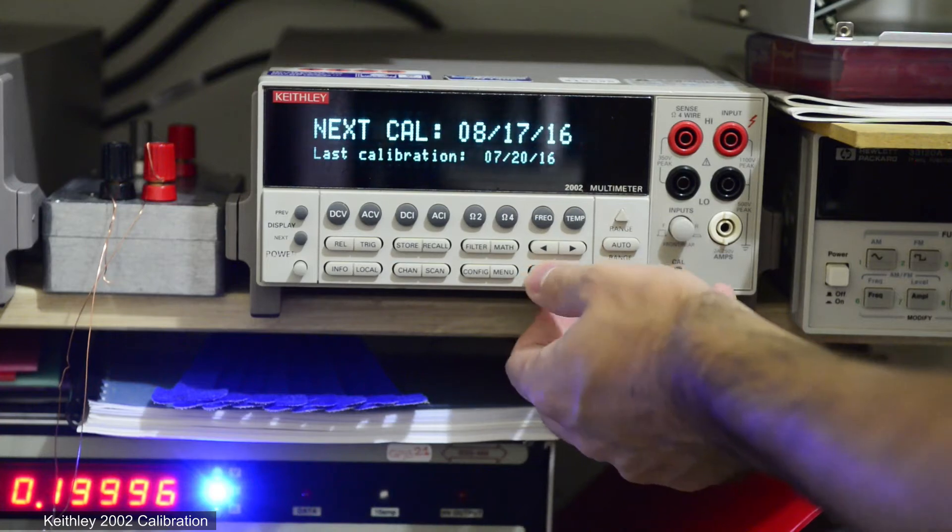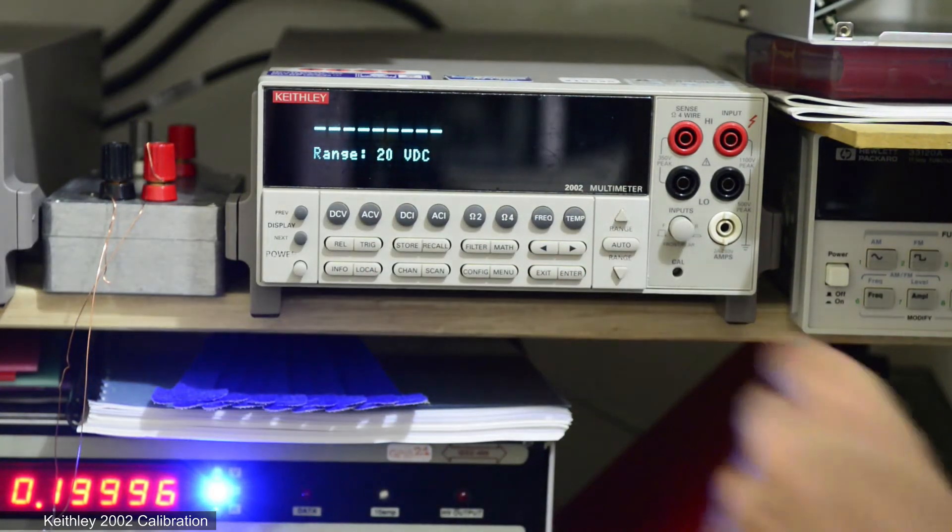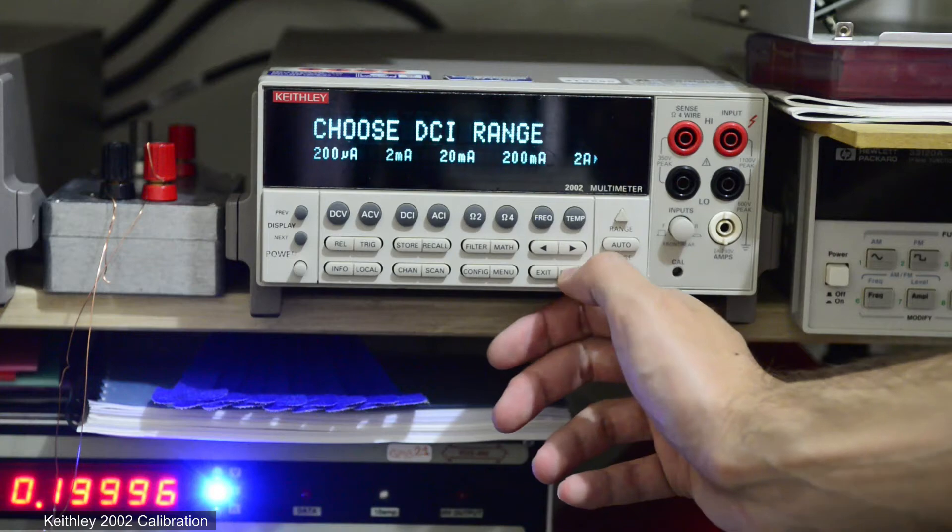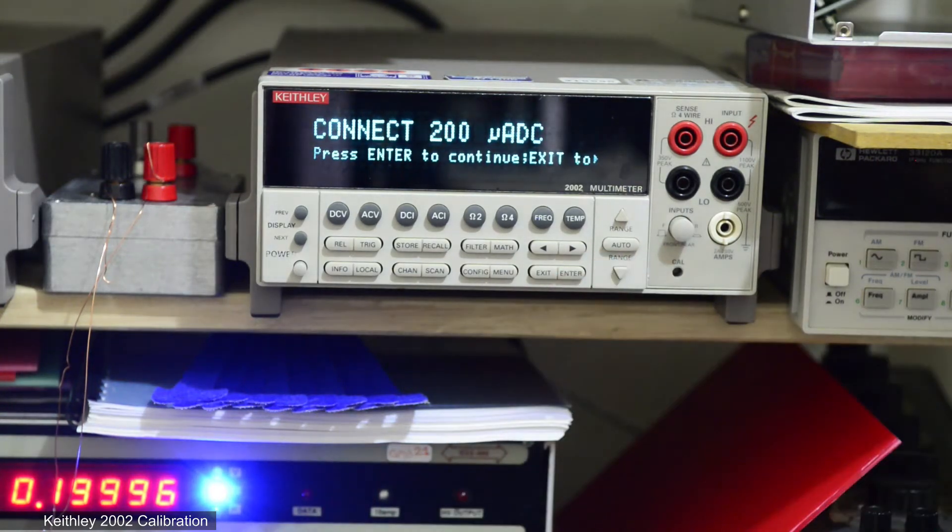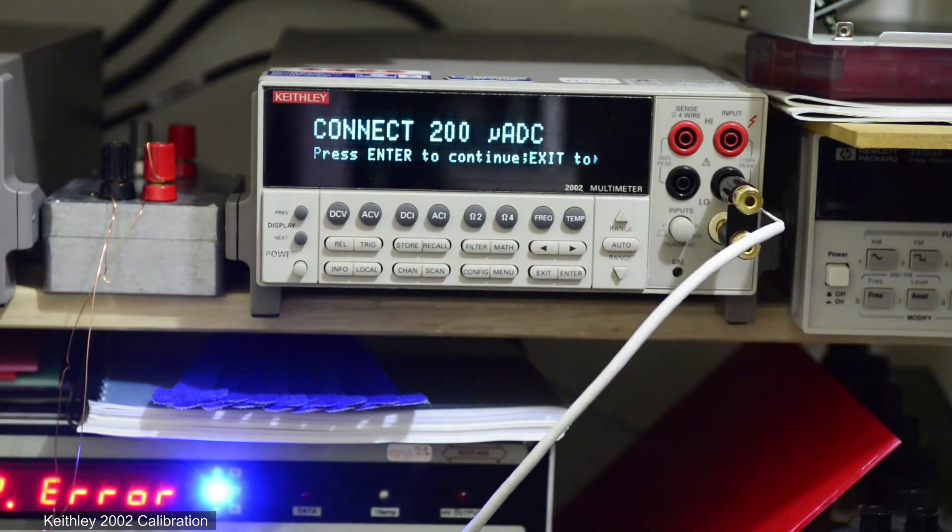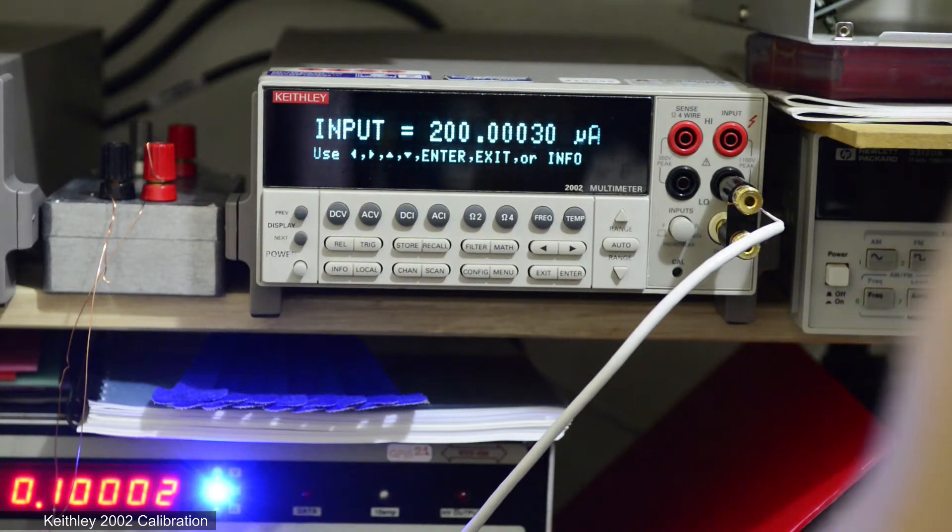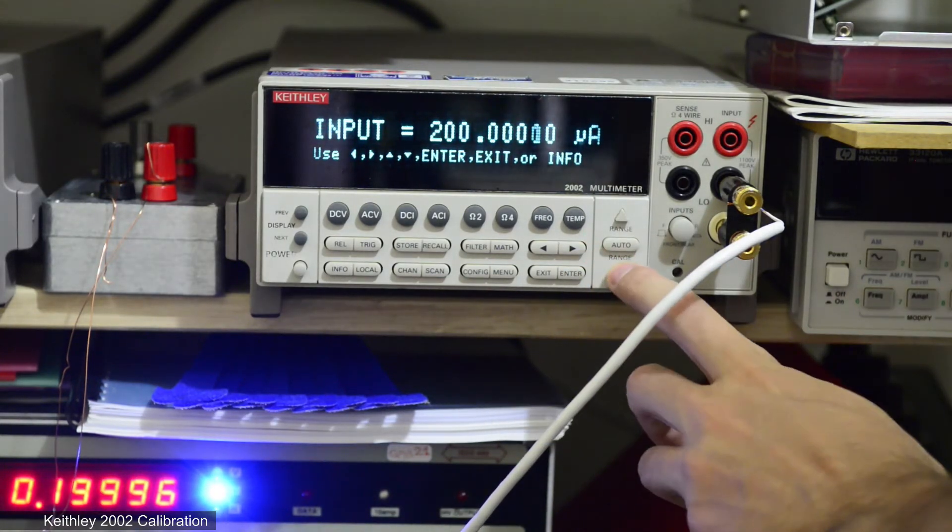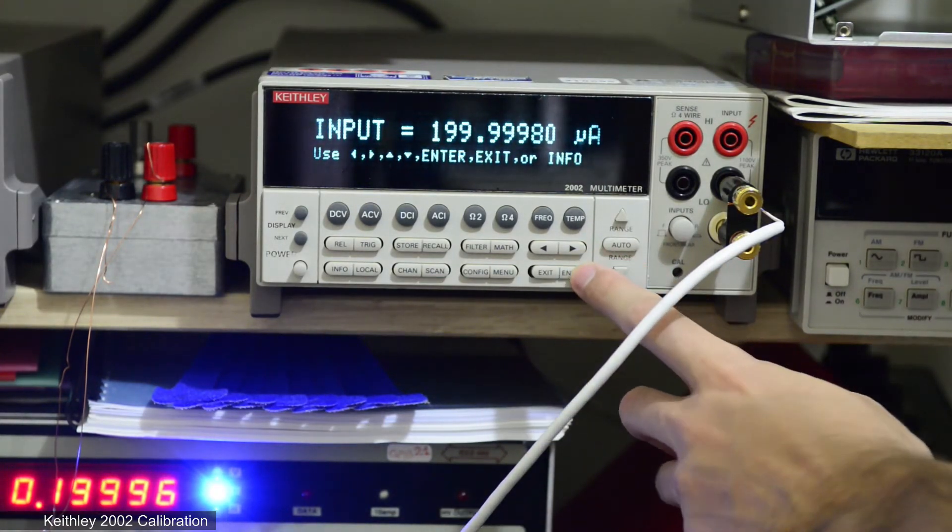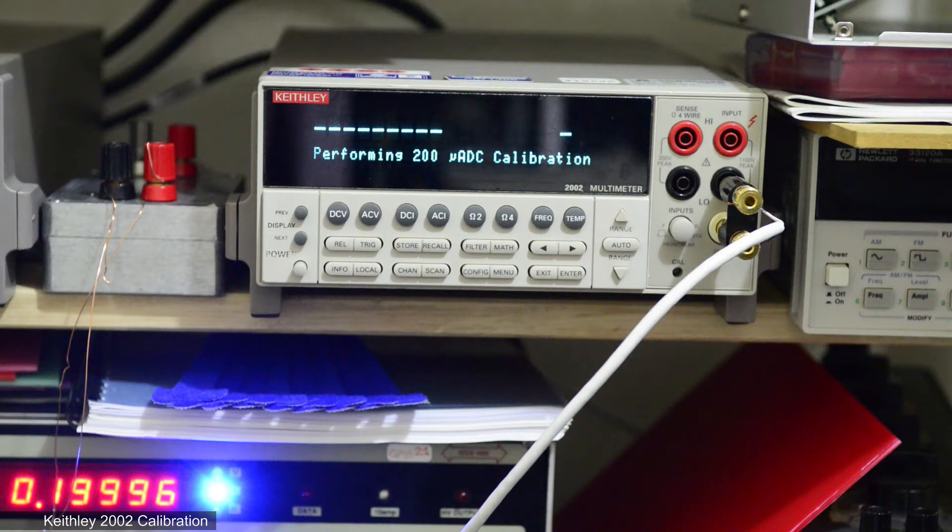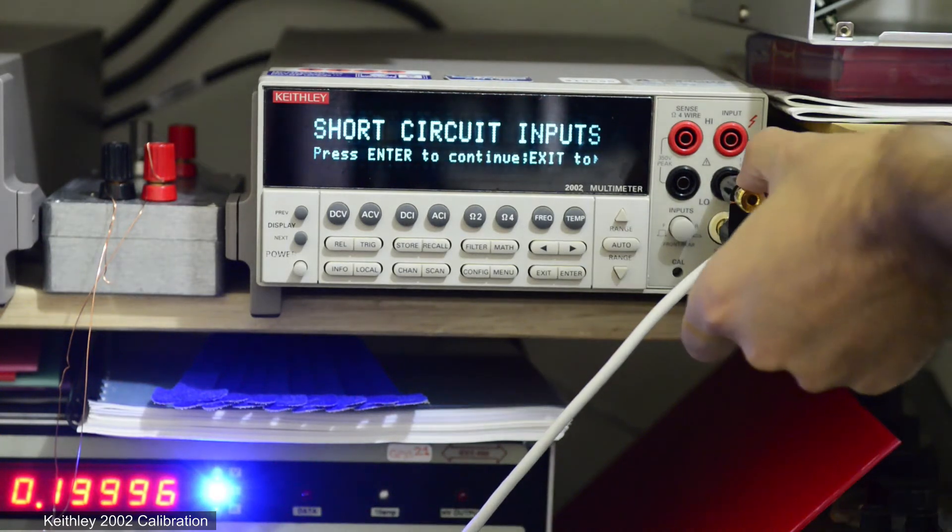Next model 2002 allows also calibration of specific points. In this case I'll just try 200 microamp again. And now using 2 milliamp range on calibrator it calibrates just fine.